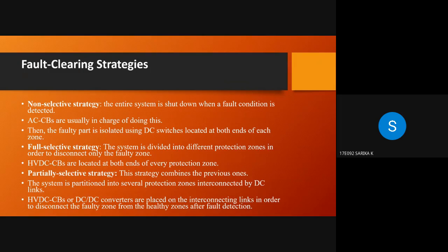Now, full selective strategy. The system is divided into different protection zones in order to disconnect only the faulty zone. HVDC circuit breakers are located at both ends of every protection zone.